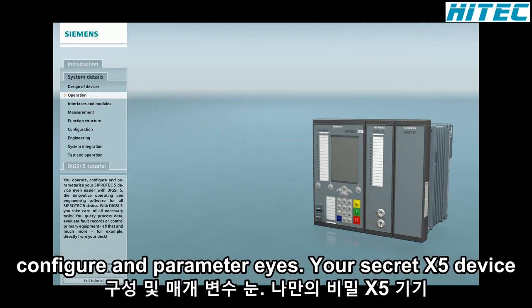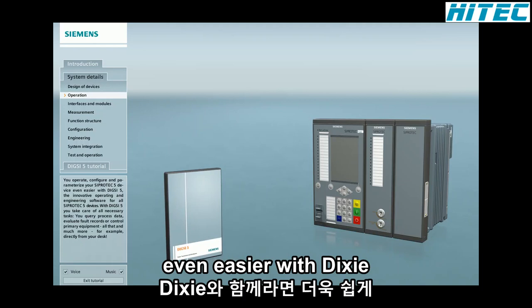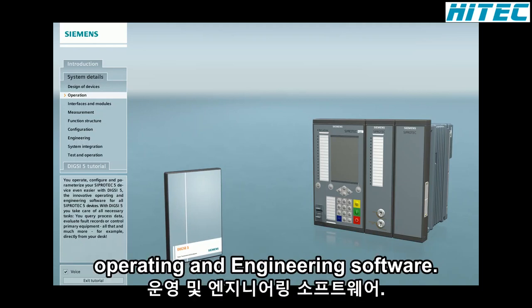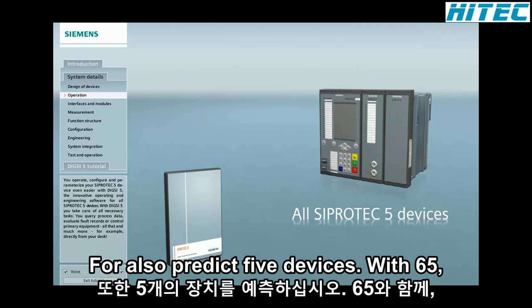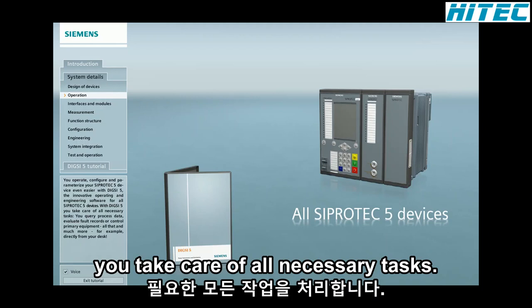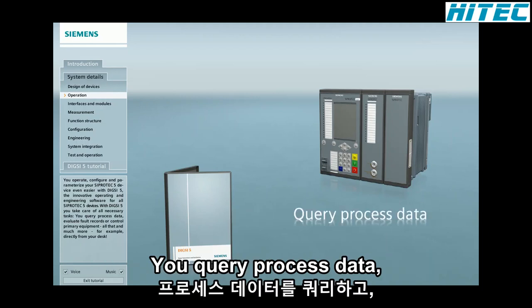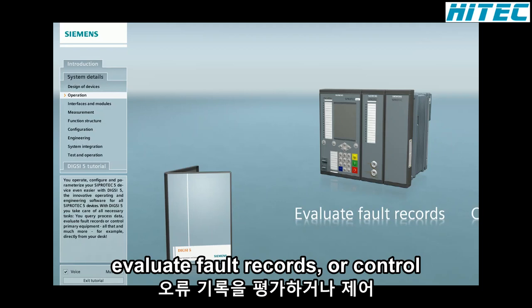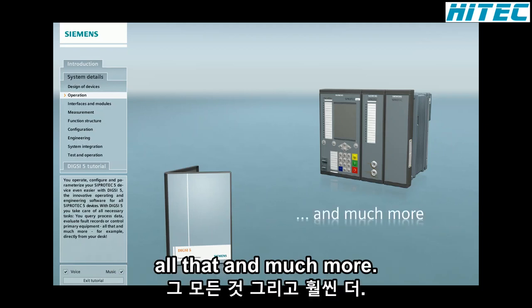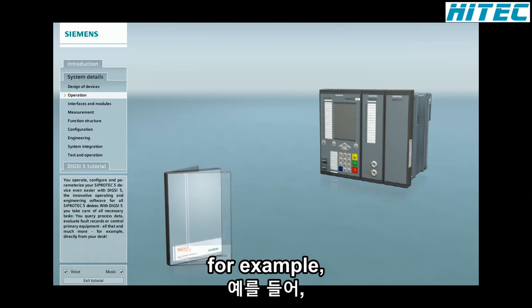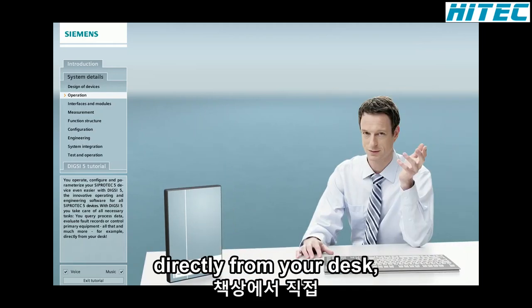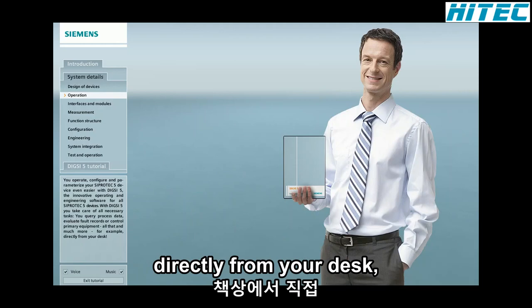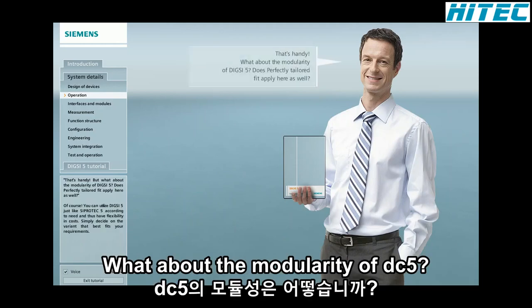You operate, configure, and parameterize your SIPROTEC 5 device even easier with DIGSI 5, the innovative operating and engineering software for all SIPROTEC 5 devices. With DIGSI 5, you take care of all necessary tasks. You query process data, evaluate fault records, or control primary equipment, all that and much more. For example, directly from your desk. That's handy. What about the modularity of DIGSI 5?